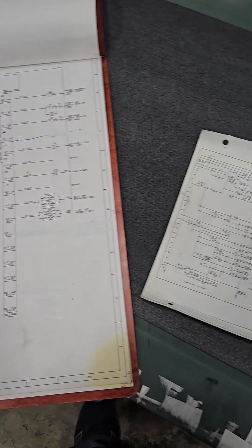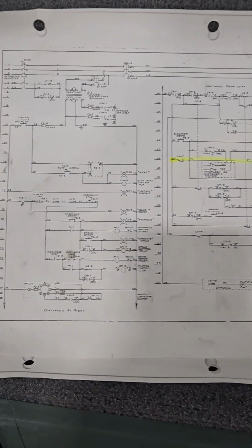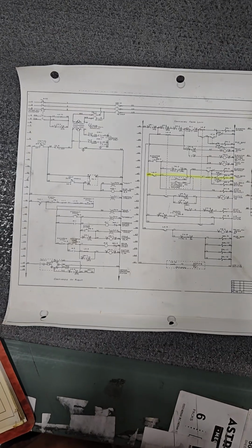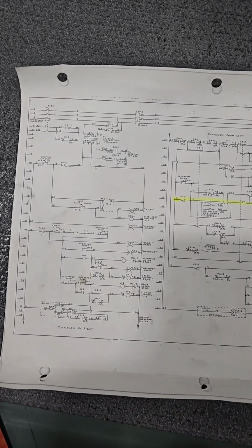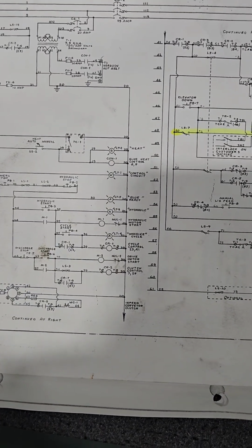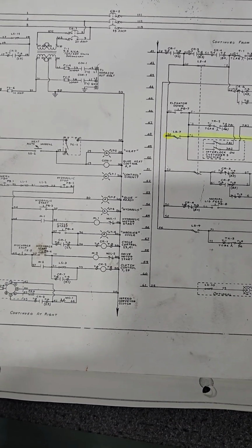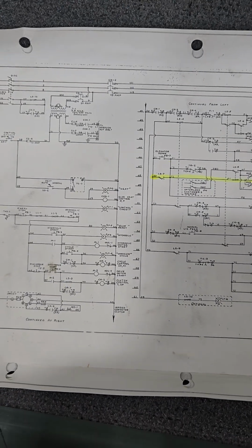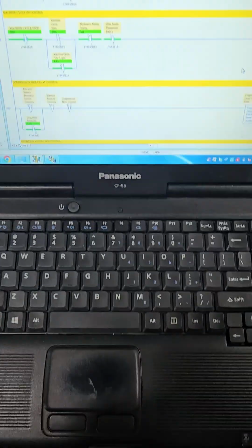Here I will show you an example of the two ladders, how relay logic is transitioned to ladder logic on the program. Okay, here is the relay logic wiring for the hardwired ladder. Here you can see the start button. It turns the machine pilot light on, and it also energizes the control relay to hold in the contacts so it stays energized when the button is released.